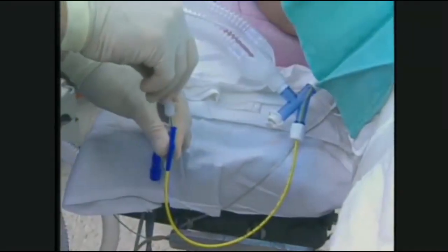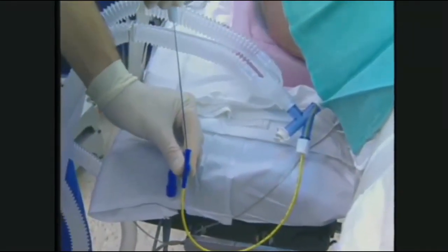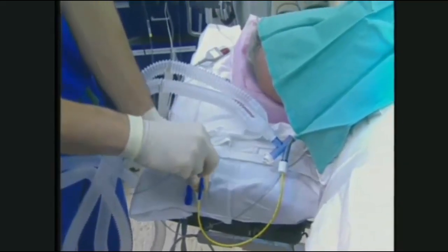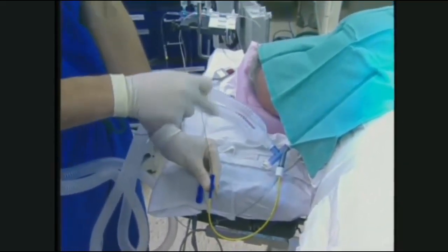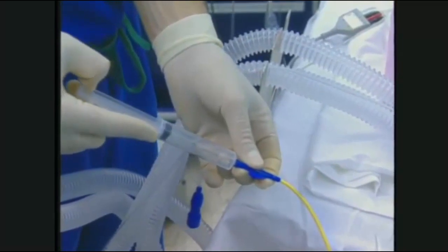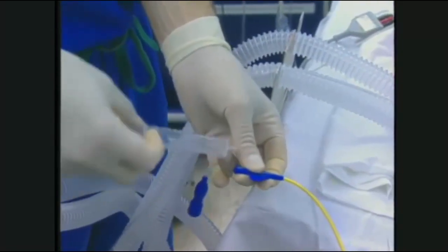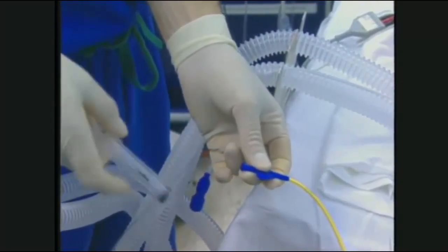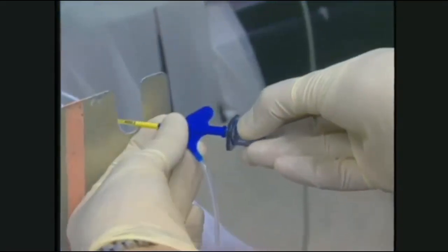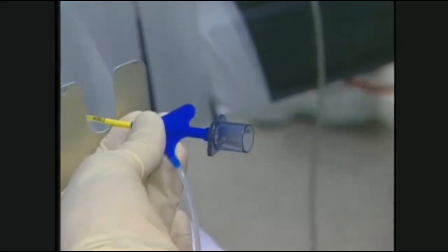Once the position is confirmed, the guide loop can be withdrawn from the central lumen of the blocker and the lung deflation can begin. The guide loop assembly cannot be replaced within the endobronchial blocker once it has been removed. Once the loop is removed from the blocker, the lung will deflate both passively and through absorption atelectasis. In addition, deflation can be assisted by direct aspiration with a syringe. The blocker's central lumen can also be used to deliver CPAP with the enclosed adapter.